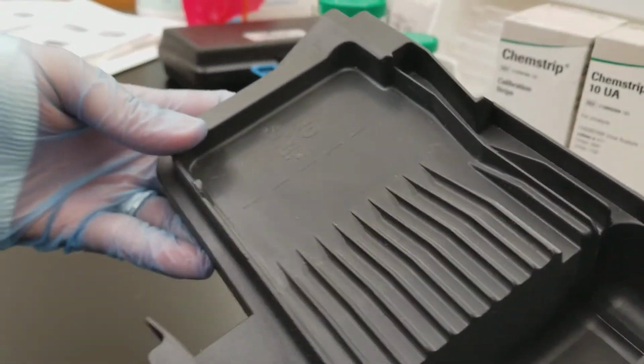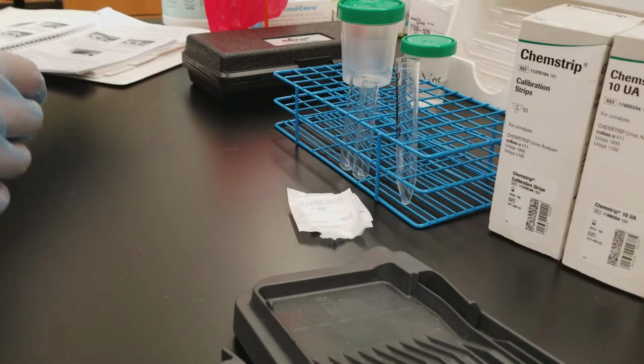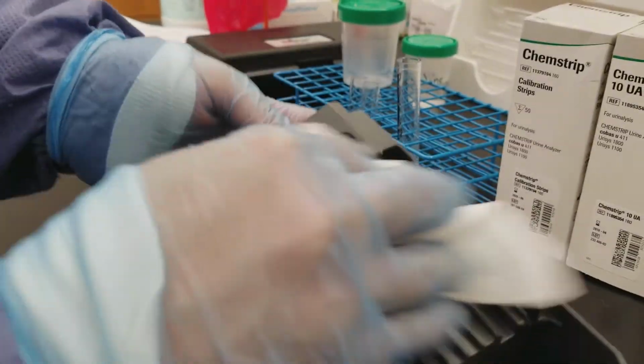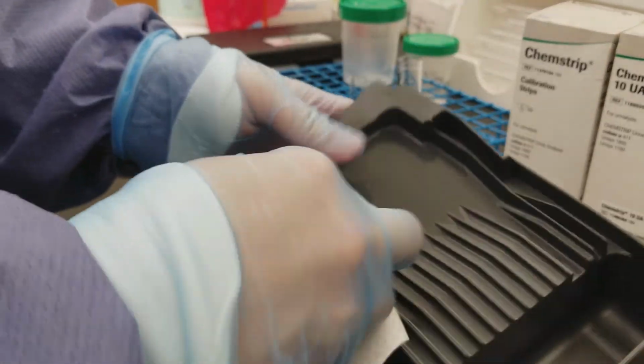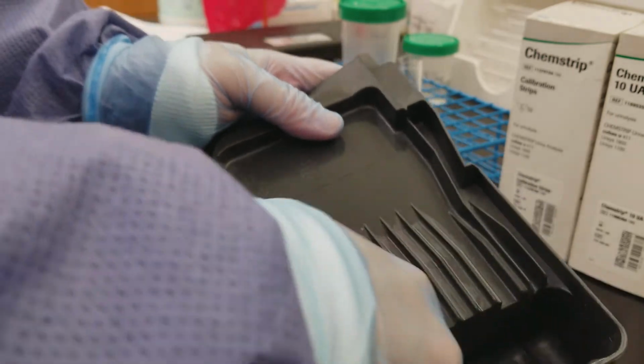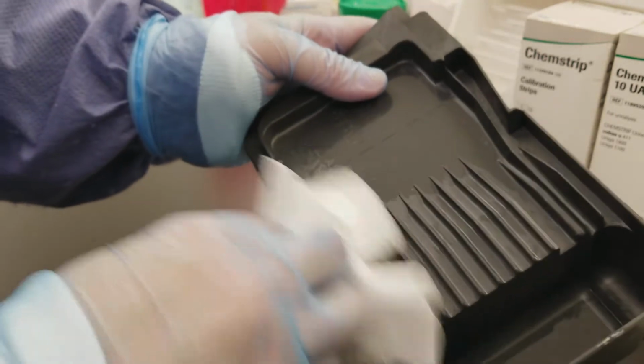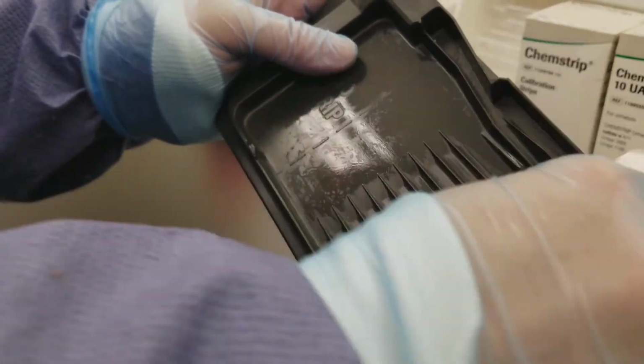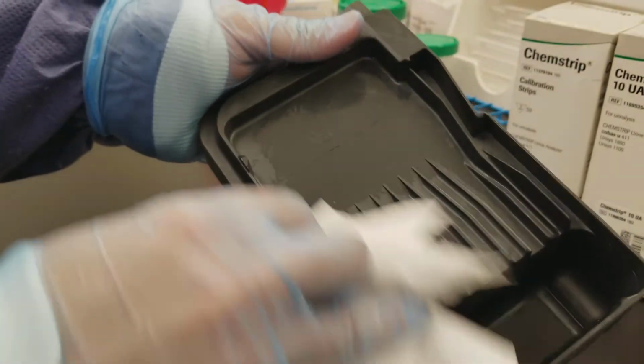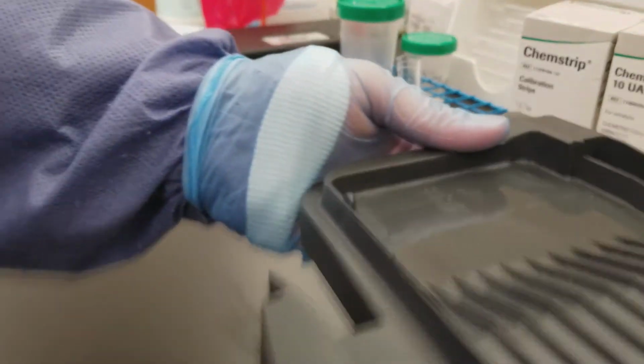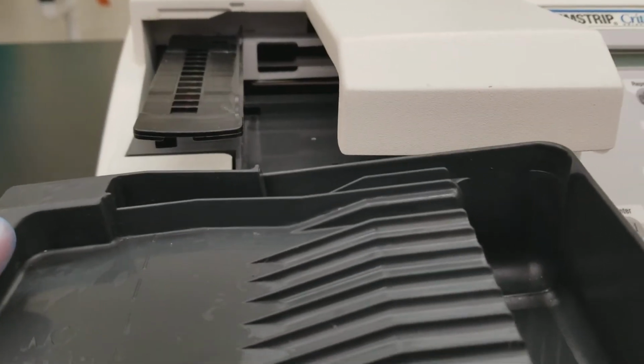There is nothing in the waste tray, but part of daily maintenance is that you go ahead and clean this off. So I'm going to use a cleansing wipe to clean the area, so that no residue or dust, or any dried up urine, is going to get onto the new strip that I would be using.